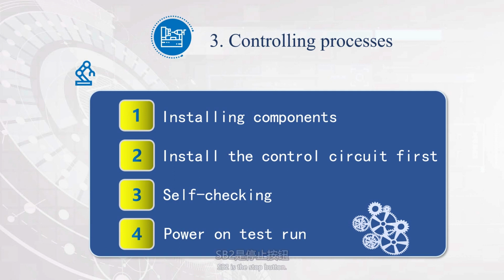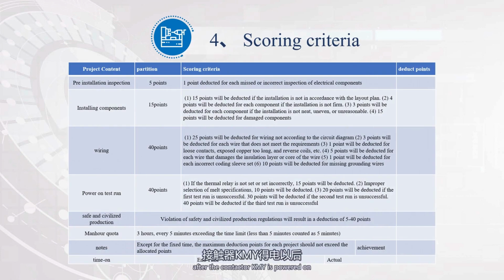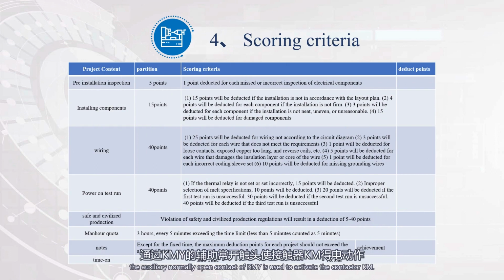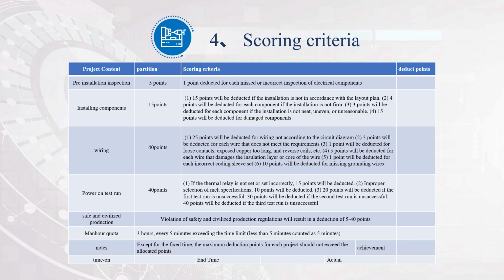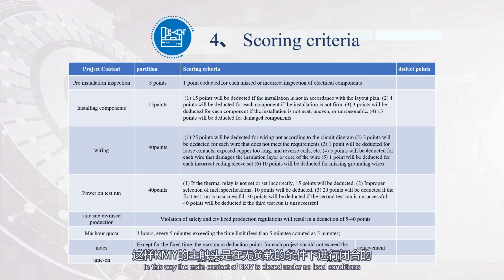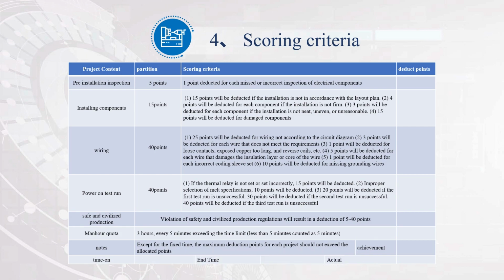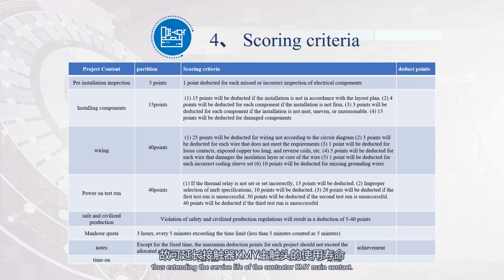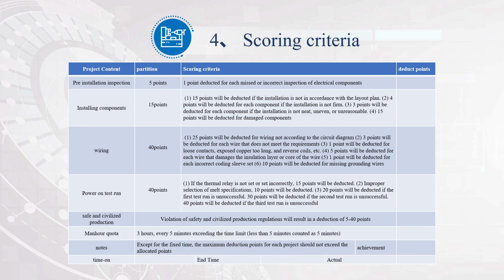SB1 is the start button. SB2 is the stop button. FU1 is the short circuit protection of the main circuit. FU2 is the short circuit protection of the control circuit, and KH is for overload protection. In this line, after the contactor KMY is powered on, the auxiliary normally open contact of KMY is used to activate the contactor KM. In this way, the main contact of KMY is closed under no load conditions, thus extending the service life of the contactor KMY main contact.